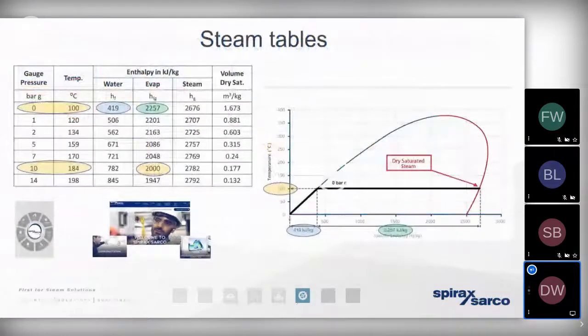So it's at this point I really want to revisit the steam tables. We know the benefit of generating steam at a higher pressure from previous presentations. At a higher pressure, the steam is far more likely to be drier and have more energy contained within it. We know that it's going to contain a much, much smaller volume, and therefore it's going to be cheaper to distribute that steam in a smaller infrastructure where we get fewer distribution losses. We get a greater efficiency.